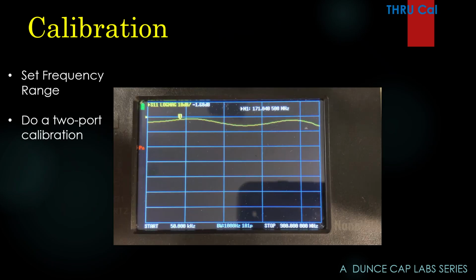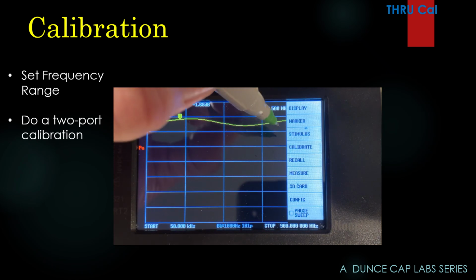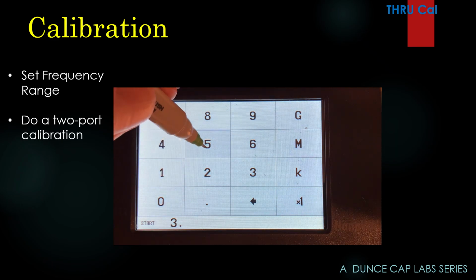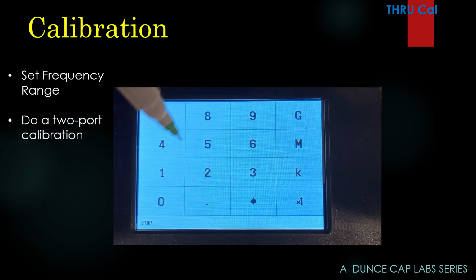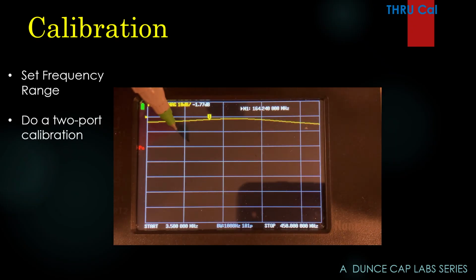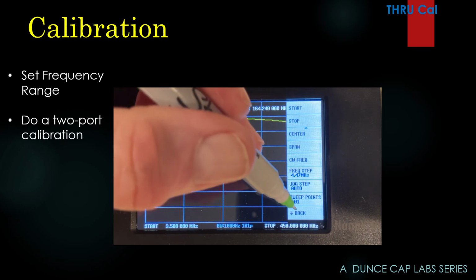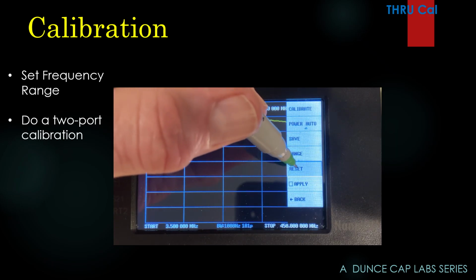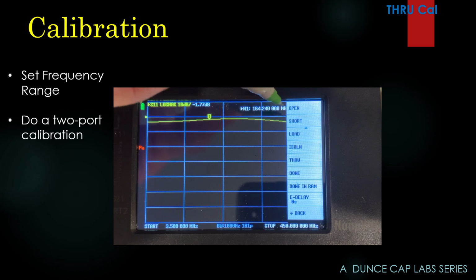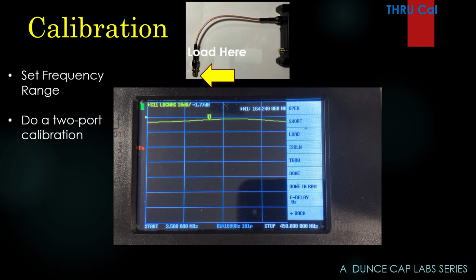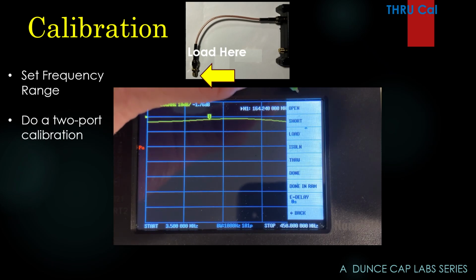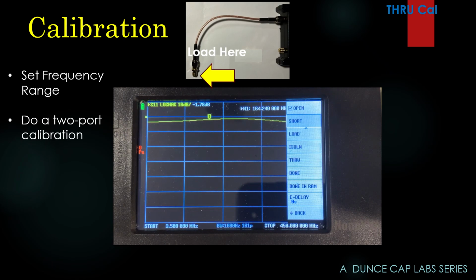So let's see if we can calibrate this thing. Start off first by setting the frequency range we want. I start with the bottom of 80 meters. And I stop at the top of 70 centimeters. And of course, it's time to calibrate. Now we are putting our terminations where we always do, at the end of the cable. There, we did it with the open terminator. Now we're going to use the short terminator.